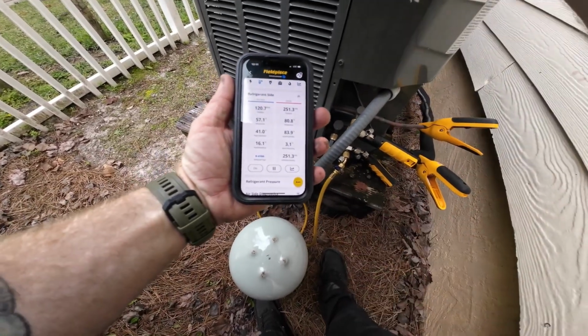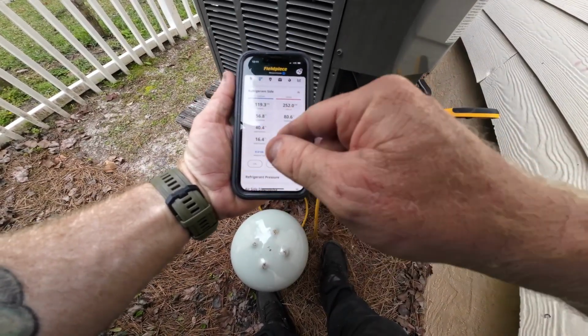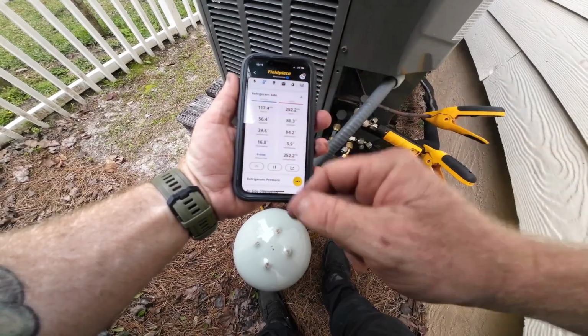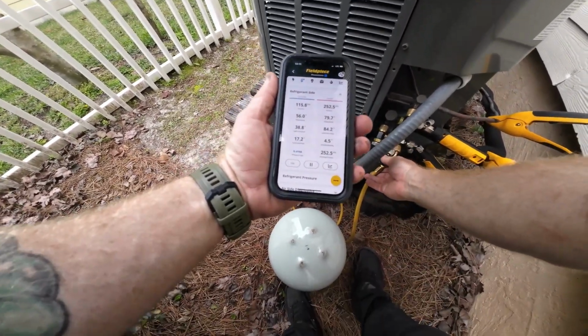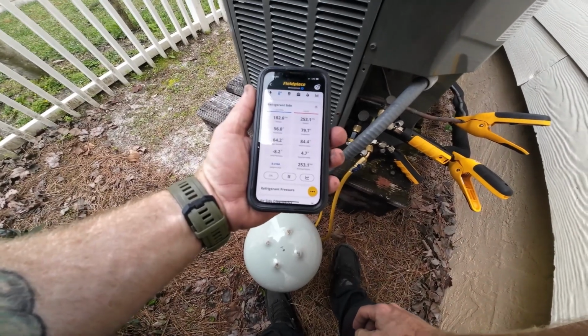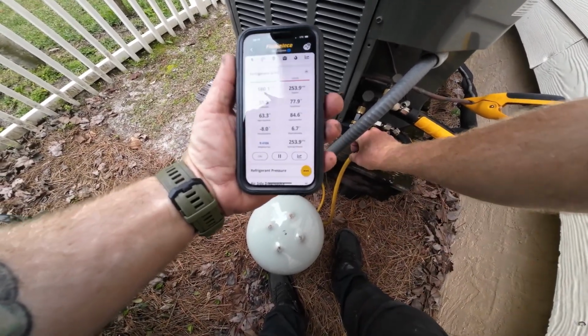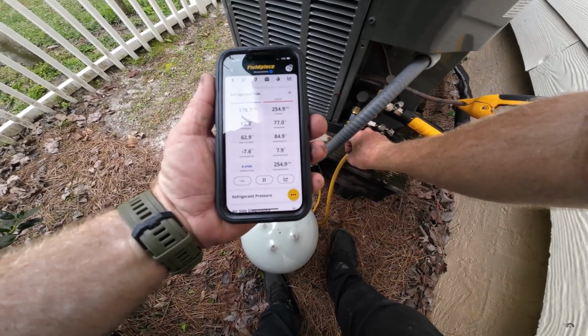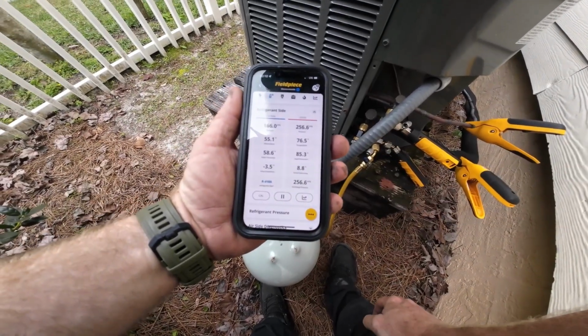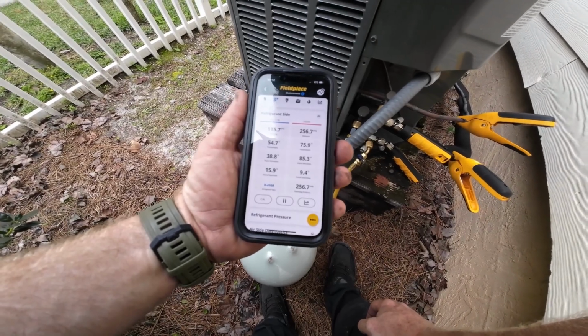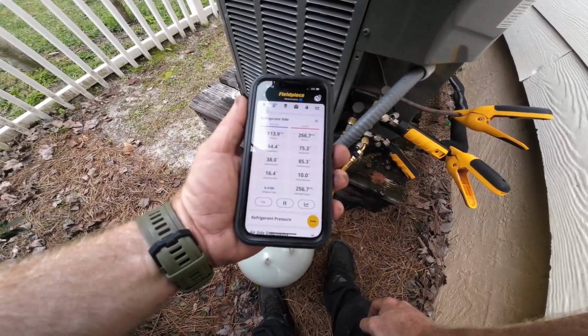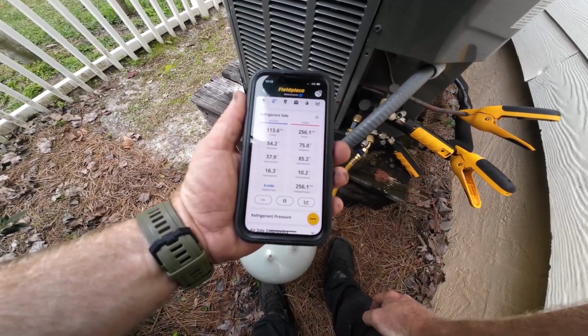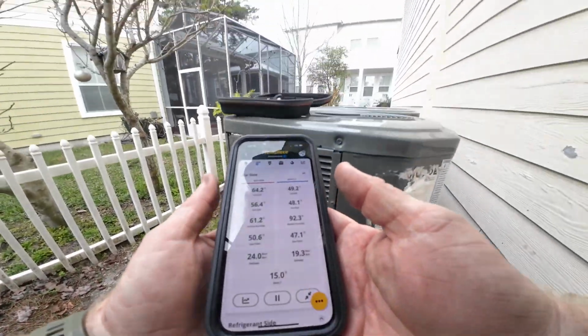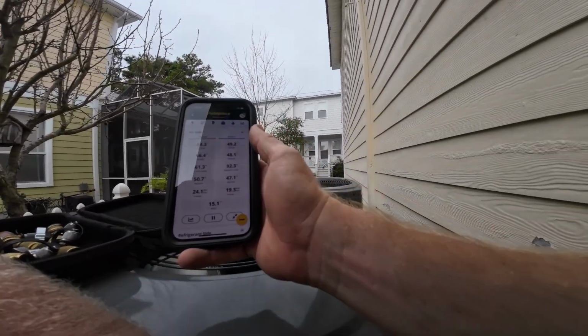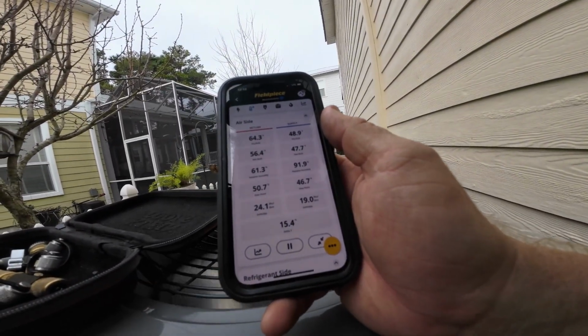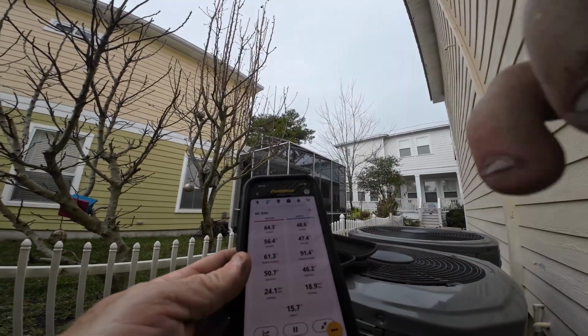And I'm going to add and see if the subcool changes, which is bouncing. That tells me there are contaminants in the system from install. We didn't install these. Another company did. But I'll get it close to 10. Right there. See, it didn't take much at all to make that thing work right. Alright, now we're going to check the temp split, see if it goes up or down. Let it run for a bit and we'll recheck it.